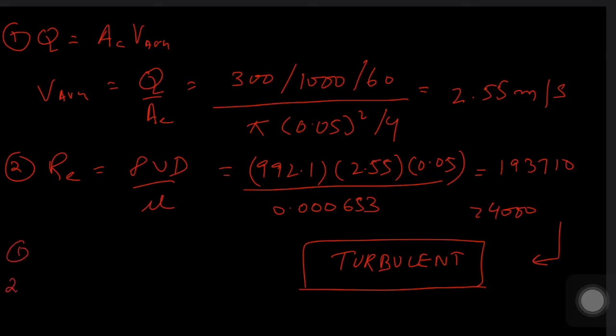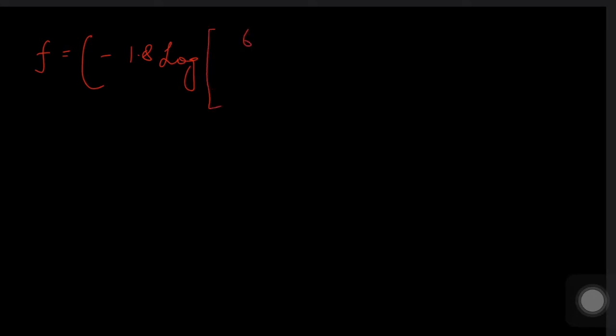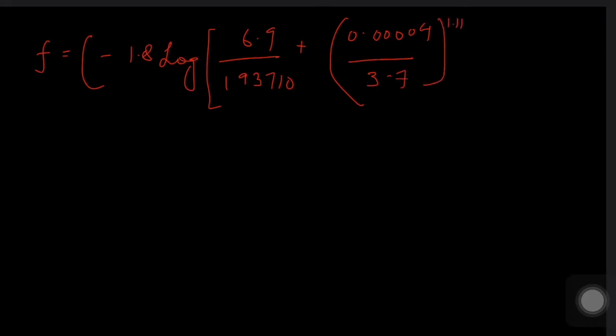Since the flow is turbulent, we use the turbulent friction factor formula. We have two options: the Haaland equation or the Moody chart. Using the Haaland equation: f = [−1.8 log(6.9/193710 + (0.00004/3.7)^1.11)]^(−2), the friction factor comes out to be f = 0.016.